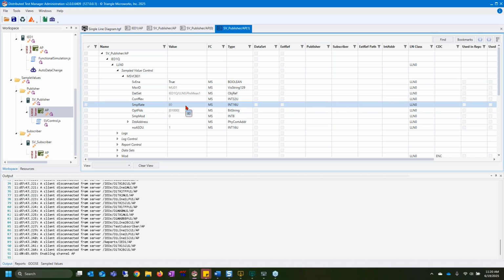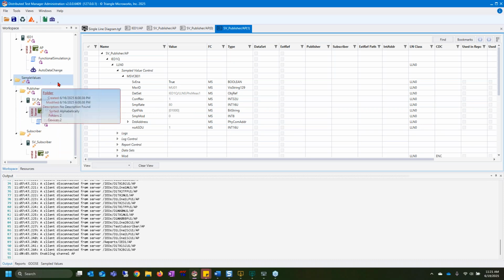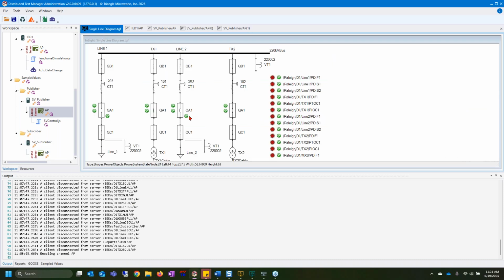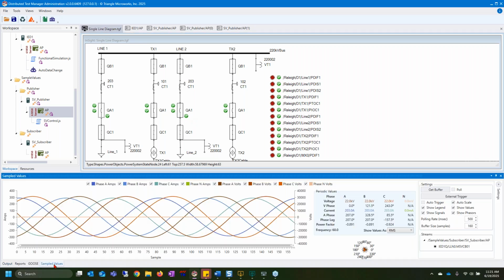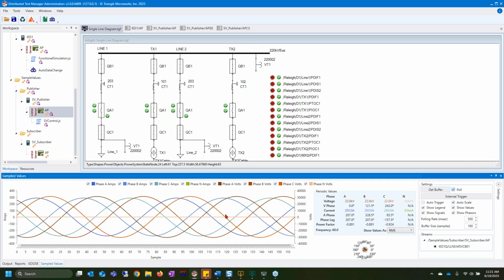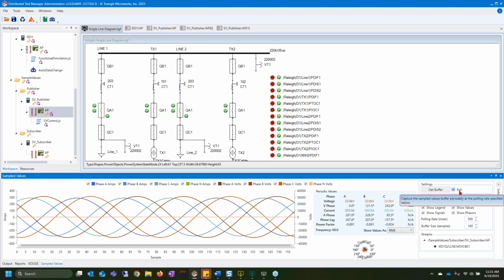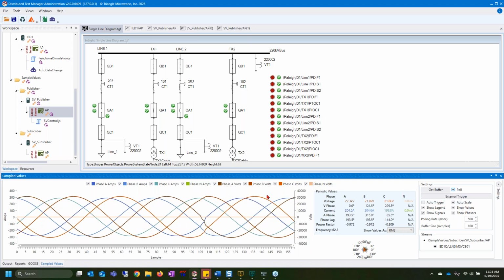So we're sampling 80 times per cycle, and we're going to be sending that out to our subscriber. So for this example, I have a folder here specifically for sampled values. I have my sampled values publisher and a sampled values subscriber. This will allow the subscriber to accurately recreate the curve that the publisher has been sampling. So I'll go back to the electrical equipment here in the single line and bring up my sampled values. As you can see, we're pulling in the sampled values. I have it set to polling right now. And we're seeing kind of this curve coming in.